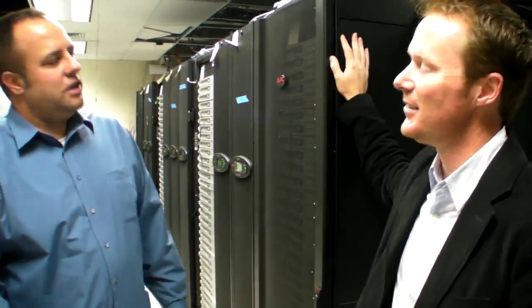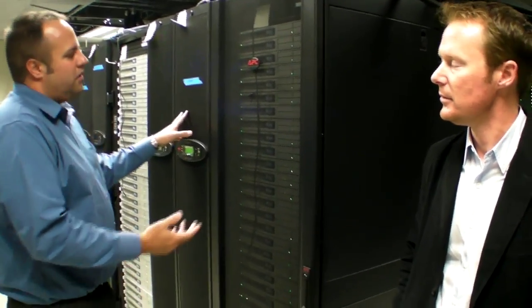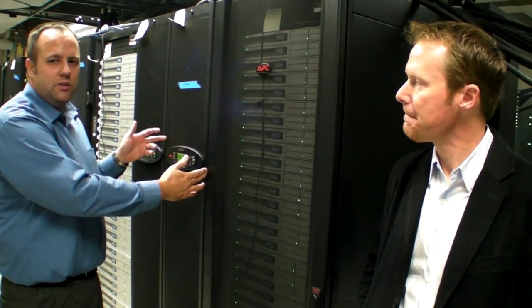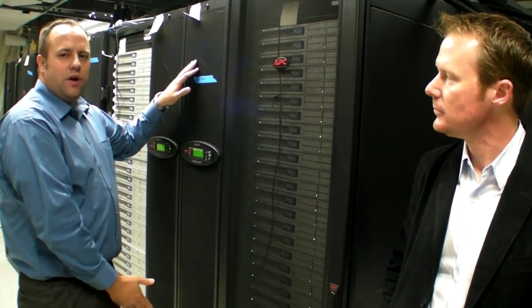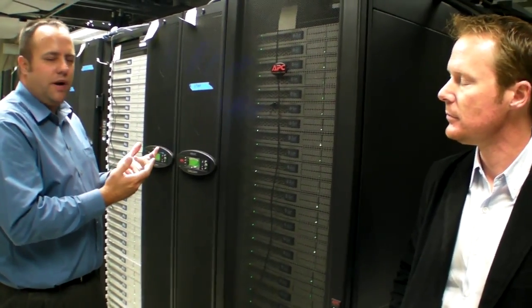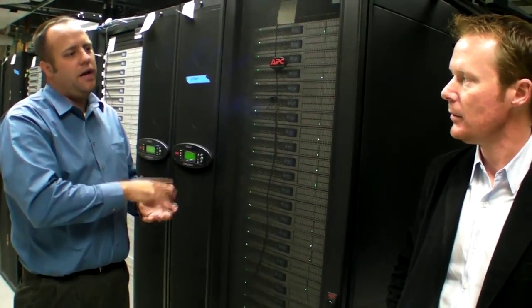The setup we've got going here is a hot aisle pod with two rows of racks and the hot aisle container system. The full unit you're seeing here is an InRow RC — it's a water-based solution, 300 millimeters wide. It's got eight fans in front of the unit, all hot-swappable, so you can replace them very easily. They also have variable speed control and will ramp up and down as the capacity changes.